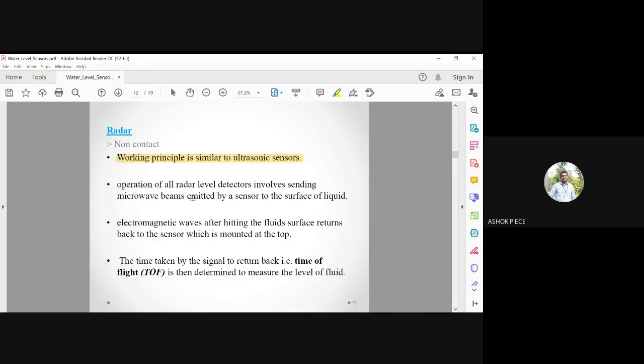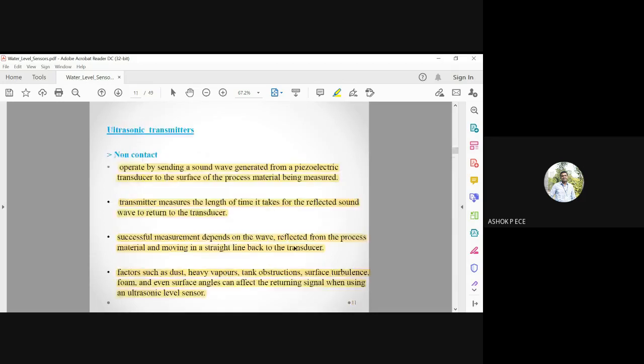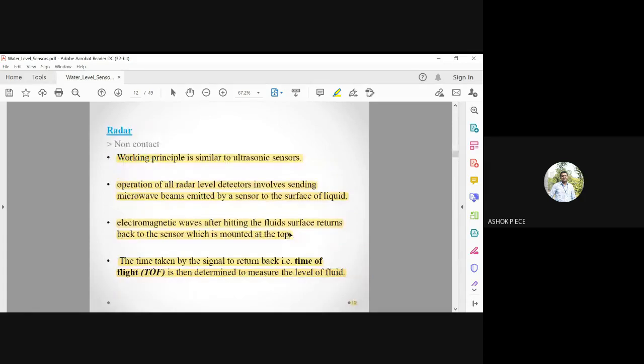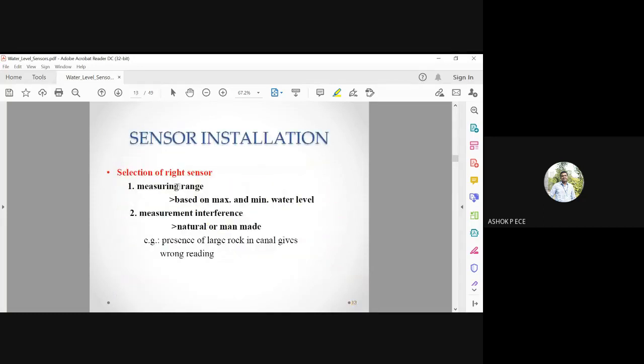The radar sensor works similarly to ultrasonic but uses high-frequency microwave or RF (radio frequency) signals instead of sound waves. Microwave beams emitted by the sensor hit the liquid surface, reflect back, and the signal is used to calculate the water level. The sensor must be selected carefully — you need to know the type of sensor, the measuring range, and the maximum and minimum water levels required for your application.